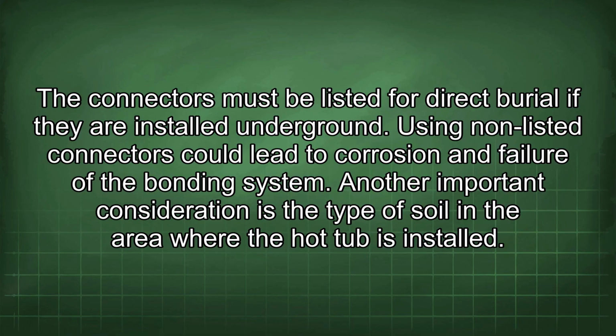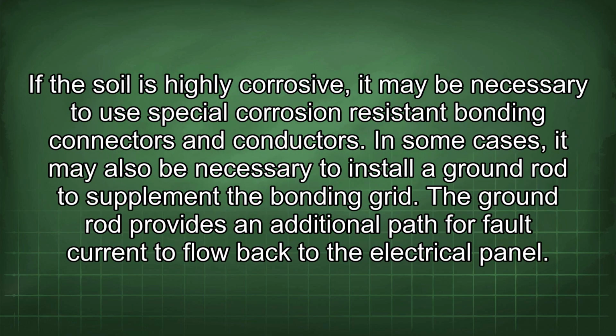Another important consideration is the type of soil in the area where the hot tub is installed. If the soil is highly corrosive, it may be necessary to use special corrosion-resistant bonding connectors and conductors. In some cases, it may also be necessary to install a ground rod to supplement the bonding grid. The ground rod provides an additional path for fault current to flow back to the electrical panel.